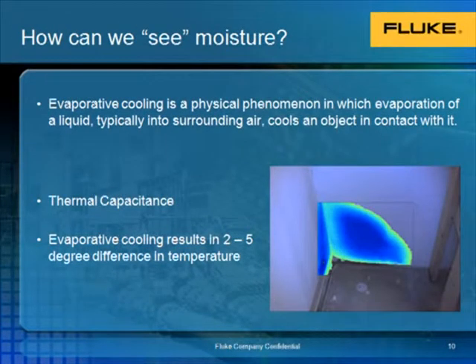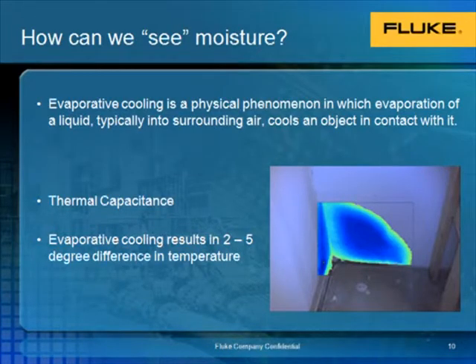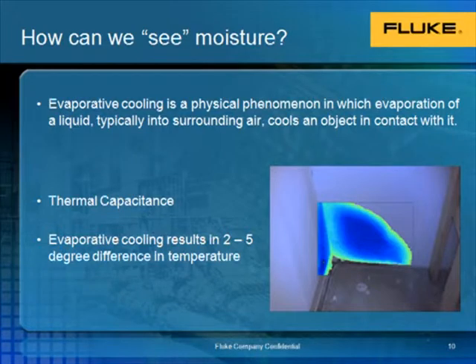You may be wondering how we're able to see moisture behind walls even though we're not able to see through the wall. We are able to do this because of what is known as evaporative cooling. When a liquid evaporates, typically into the surrounding air, it also cools an object it is in contact with. Thermal capacitance comes into play as well — this deals with a material or liquid's ability to retain its energy. Because moisture or water has a high thermal capacitance, it retains that energy much longer than other materials.